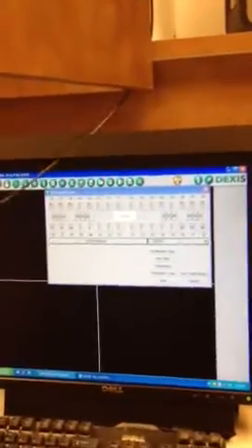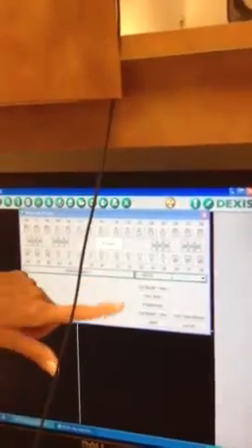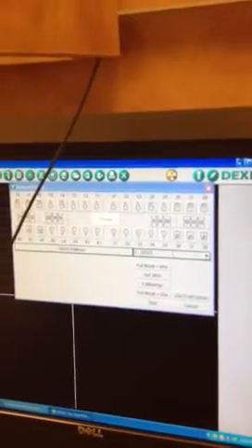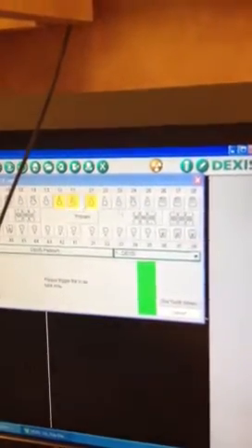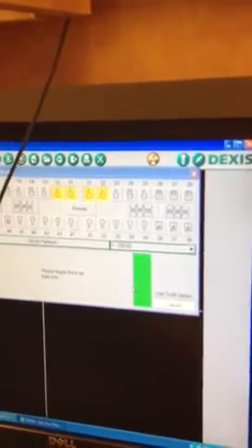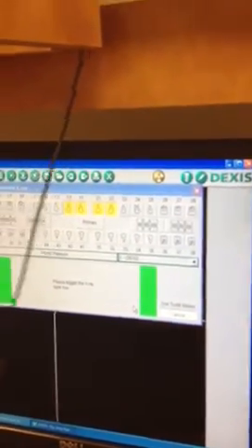Okay, so here we can see that there's no more yellow bars on the side, and when I pick what we want to expose, we'll either be exposing a full mouth series with 2 bite wings, 4 bite wings, and if we choose one of those tabs, it will actually guide us through in the sequence that we should take them. If we're just taking individual, then we should be selecting the actual teeth that we want to expose and then coming back and doing that again before we carry on. So right now, I will just select the teeth, so I'll do an anterior maxillary PA. So now it's green, so we know that we could go ahead and expose.